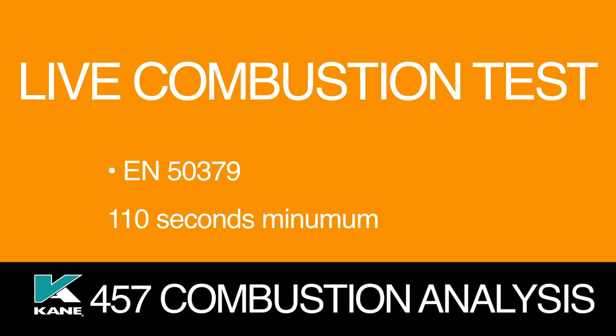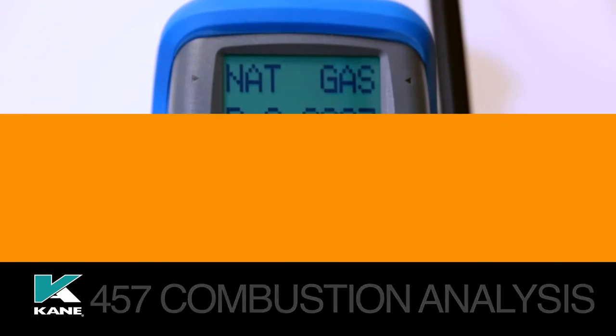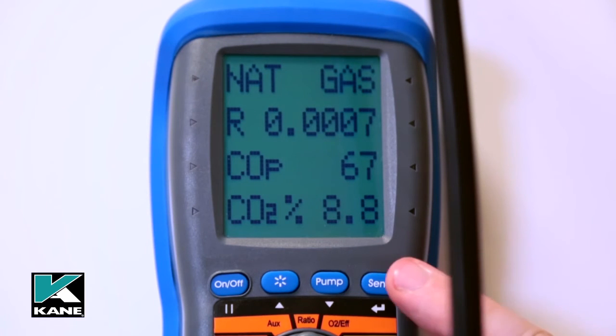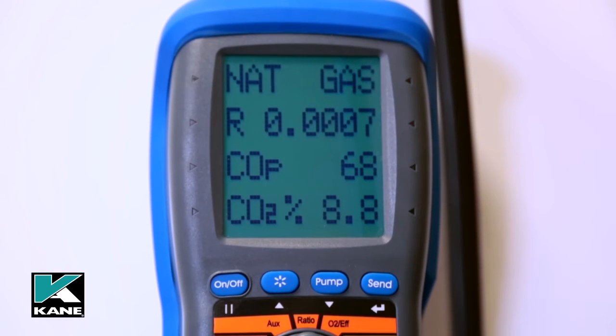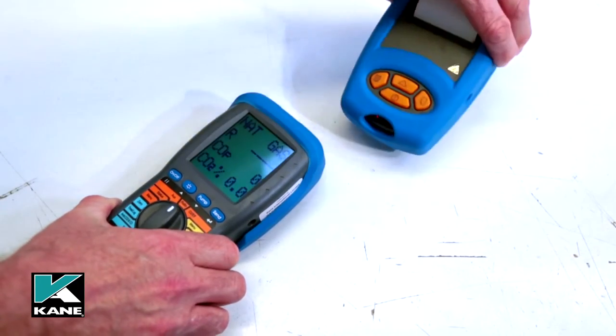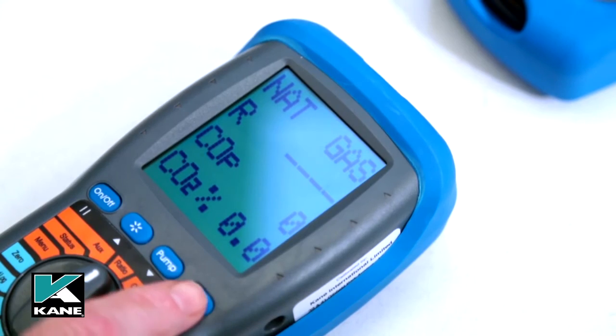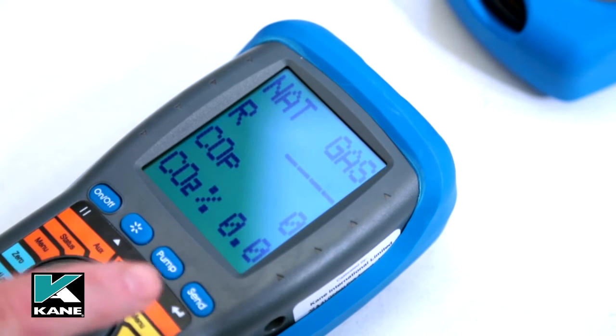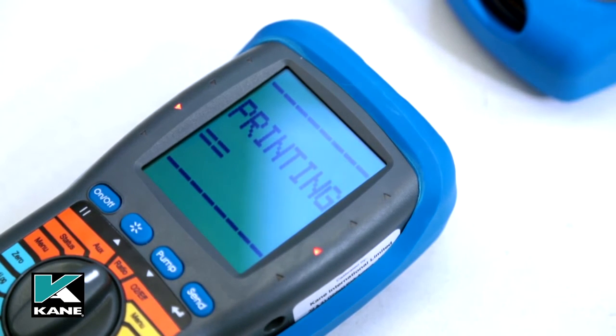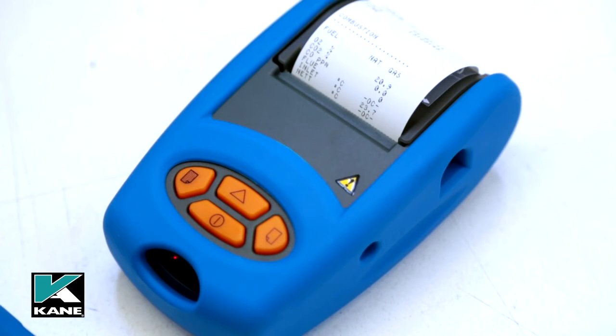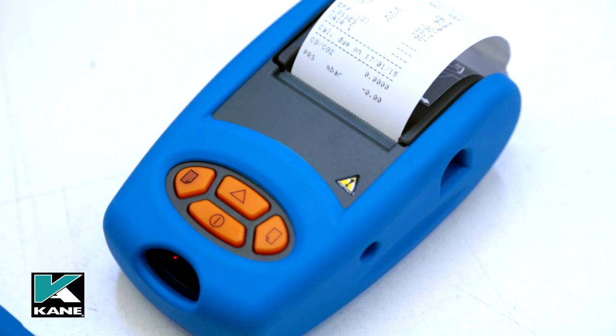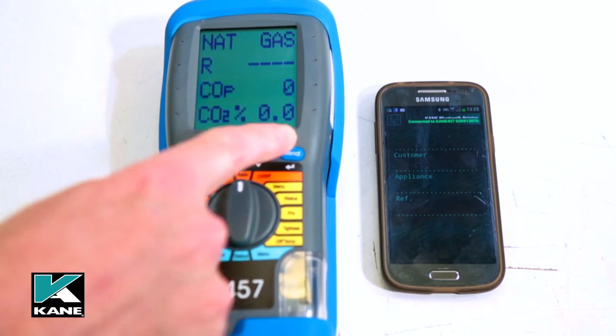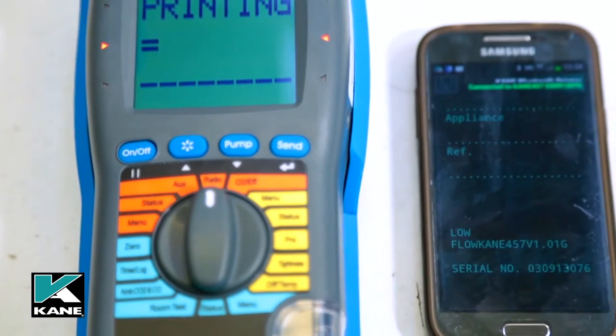Once the readings have stabilised, refer to the manufacturers' instructions as to what the readings should be. The readings can now be stored in the internal memory by pressing and holding the send key until a log number appears on the top line — this is now stored for further reference or printing at a later stage. To print a reading, align the printer to the analyser as shown. Make sure the printer is switched on and a short press of the send key will transmit the readings to the printer. The printout will be a full combustion report including ratio, flue temperatures, losses, and excess air — everything you need for a full combustion report. If the optional Bluetooth module is fitted, these readings can also be sent to a PC or Android phone.